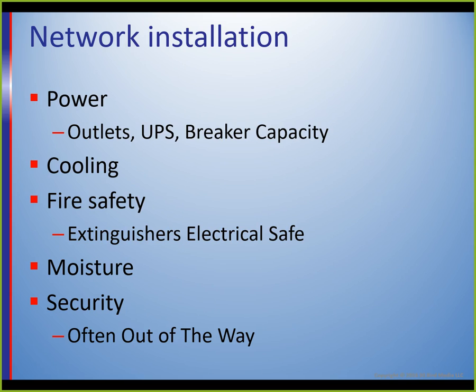Fire safety, extinguishers need to be electrical safe. What are you going to use in the NOC? And when we looked around, we said, there is a water flooding system that goes through here. Do we want to disable this thing and use fire extinguishers, CO2 extinguishers in here? And the answer is, yeah, we would like to use CO2 extinguishers in here and not water.